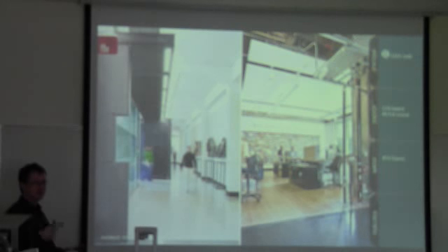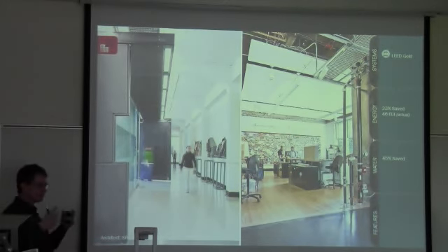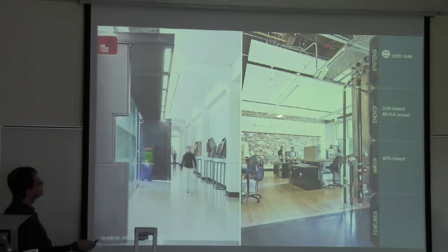Very efficient. Systems are already in place. All we had to do is take out the old air handler and put in a new dedicated outside air handler in that space. And then the radiant panels, you can see them here within the space. They're off of these closets that are adjacent to the room. And there's one off the photo right here. The closets have the valving that change over the panels from heating to cooling. And so it's actually been very well received.